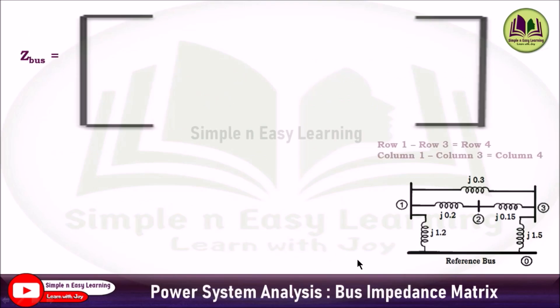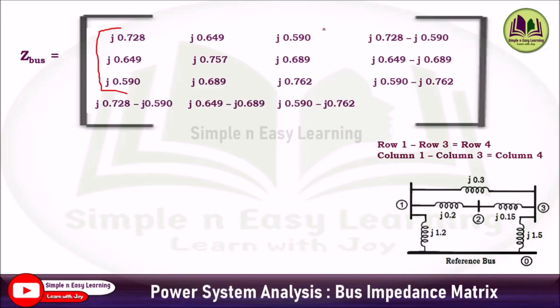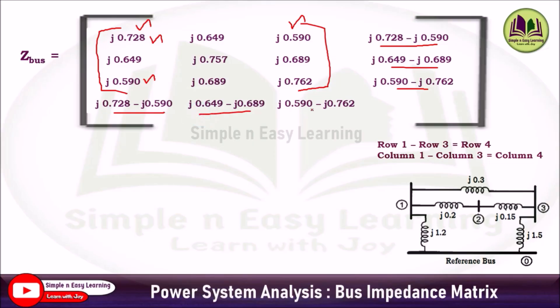We use row 1 minus row 3 for row 4 and column 1 minus column 3 for column 4, because the reactance j0.3 is connected between bus 1 and bus 3. Starting from the 3×3 matrix obtained after step 4, the fourth column is: Z11 − Z13 = 0.728 − 0.590, and similarly for the other elements. The fourth row is obtained in the same way.